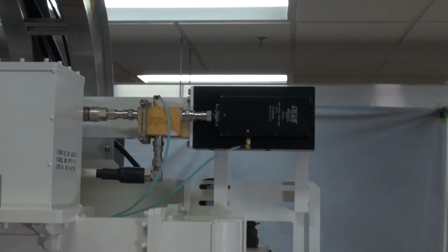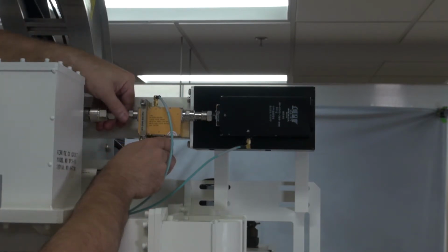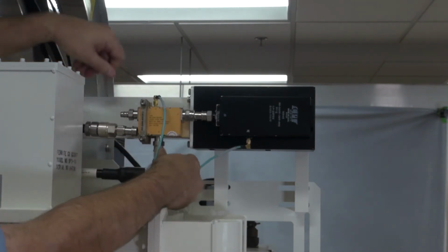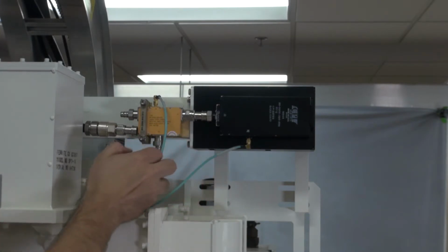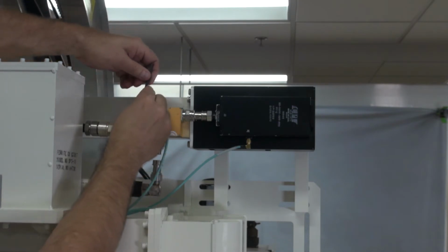Disconnect the horizontal LNA if it is not already disconnected. The sequence of removal procedure reduces the risk of damage to the LNA. Disconnect cable 2W556 and 2W577 from the LNA. Remove the LNA clamp.